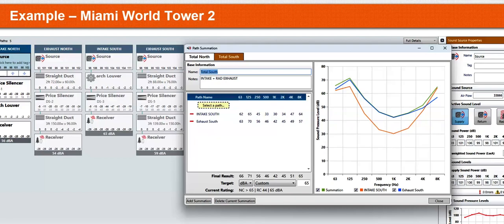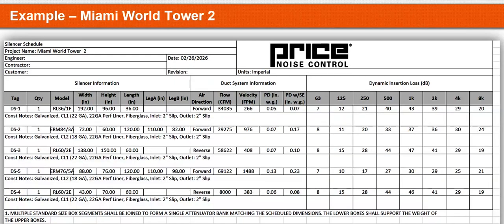In this specific case, at the design stage, I sized a couple of silencers for the radiator exhaust. We lined 70% of the concrete room with wall mount acoustical panels and also added 4-foot long silencers to get to 65 dBA at the nearest line of sight, which by the code in that specific BC city area was acceptable. I schedule the minimum pieces of information for the silencers that can be done at the design stage for both the inlet and discharge, including insertion loss per octave band, ideal tested pressure drop, and installed pressure drop with system effects. So very important.